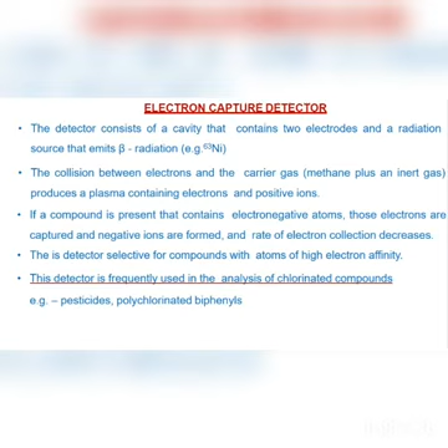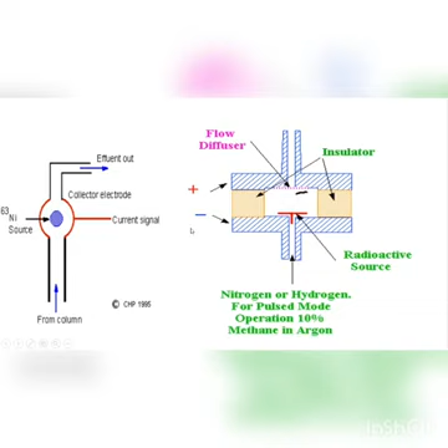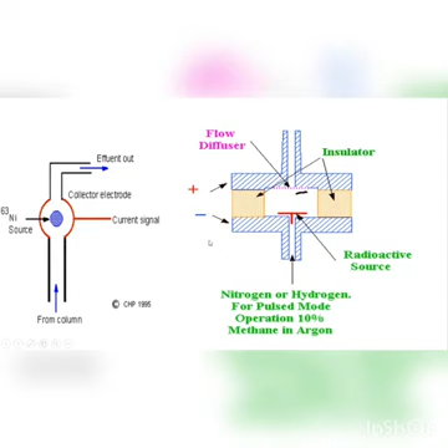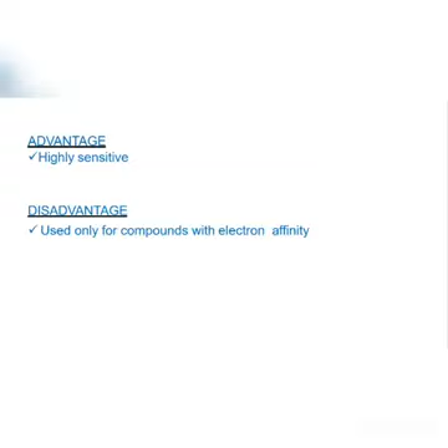In this figure, the detector contains a radioactive beta particle source, which is nickel-63, a cathode and an anode. A mixture of CH4 and nitrogen or argon is used as the carrier gas. The advantage of this detector is that it has high sensitivity, and the disadvantage is that it is used only for compounds which have electron affinity.